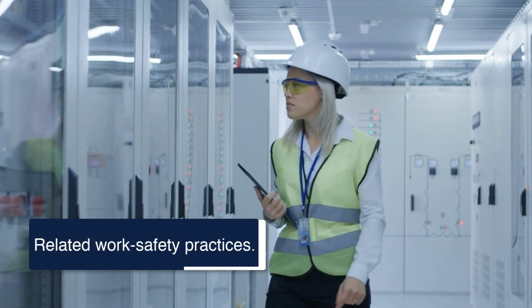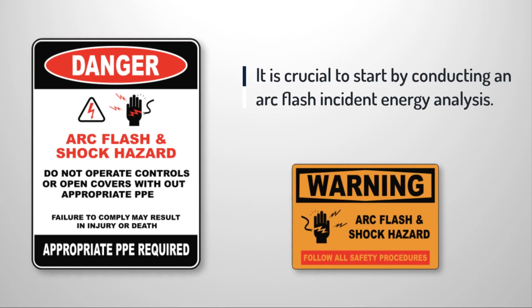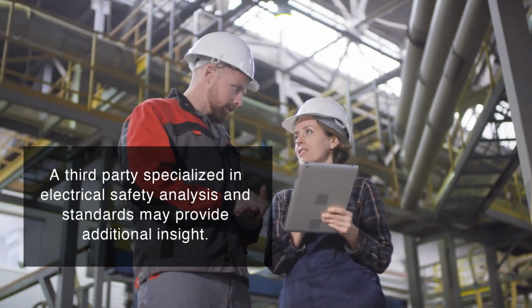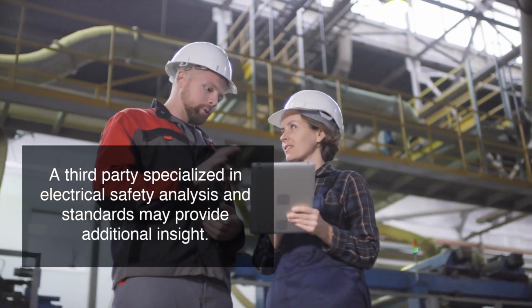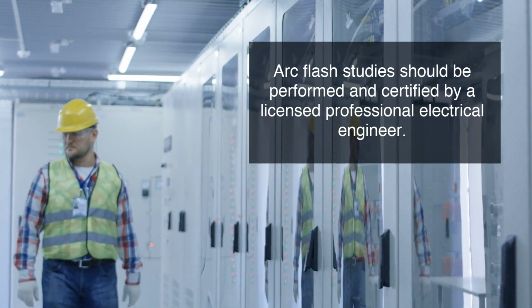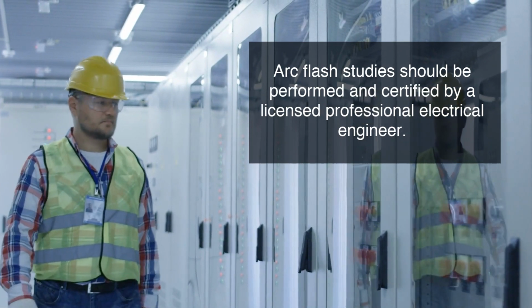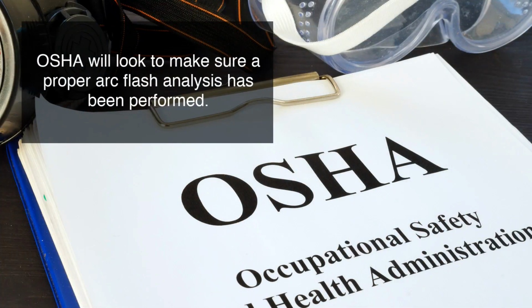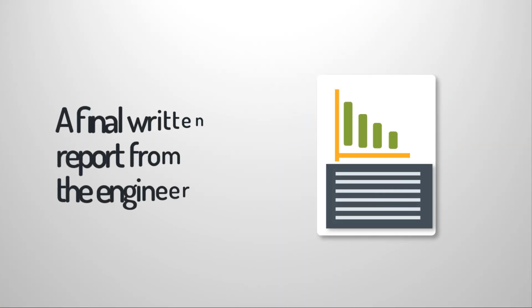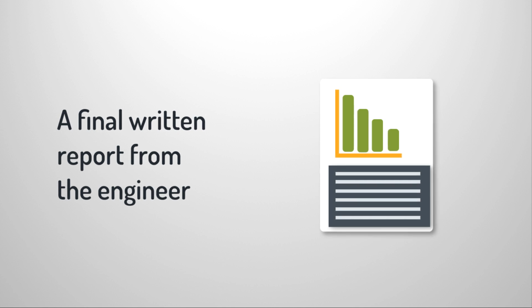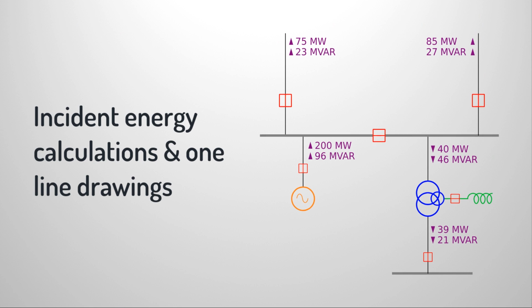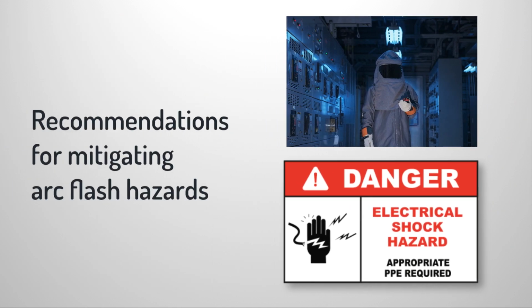These assessments are complex, and it's crucial to start by conducting an arc flash incident energy analysis, possibly with the help of a third party that specializes in electrical safety analysis and standards compliance. Any arc flash study should be performed and certified by a licensed professional electrical engineer. In the event of an arc flash incident, OSHA will look for documentation that an accurate arc flash analysis has been performed. A final written report from the engineer or engineers conducting an arc flash study will include incident energy calculations, electrical one-line drawings showing incident energy levels at specific points, and recommendations for mitigating arc flash hazards.